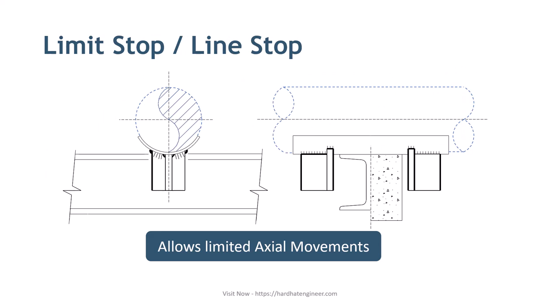Next is limit stop, or line stop. A line stop is used to prevent excessive line travel on the pipe rack — it restrains a pipe from moving along its length. This is opposite to the guide, which allows free axial movement. Note that the line stop does allow a predetermined axial movement, as you can see in the image where there is a gap between the stop and the beam. It will allow the pipe to move only by that predefined gap, restricting any additional movement beyond the allowable limits. So when the line expands and hits the stop, it will not allow further expansion beyond that point.